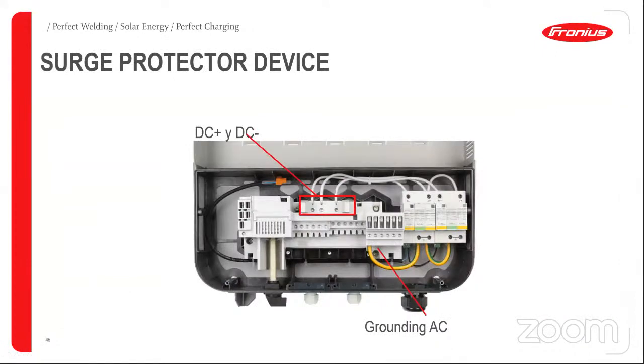So we see here an example of the connection of the SPD. Something also very important is that we can connect the SPD to the display of the inverter. In case the SPD has a damage or has been activated, this connection will send a message to your cell phone or to your email, so you know that the SPD has already been operated. So you need to change the SPD to again protect the installation.